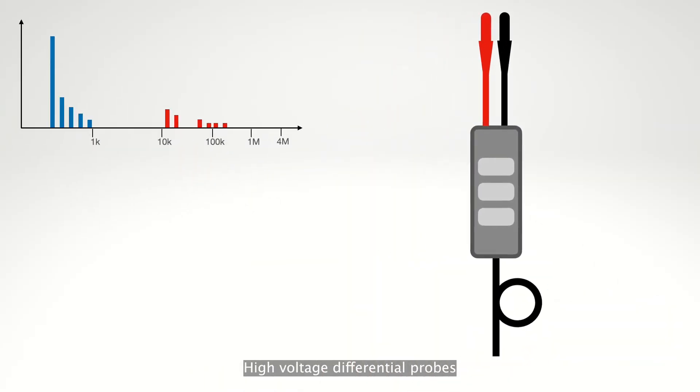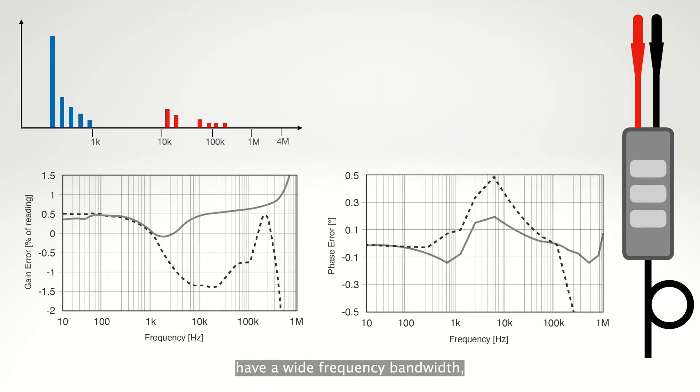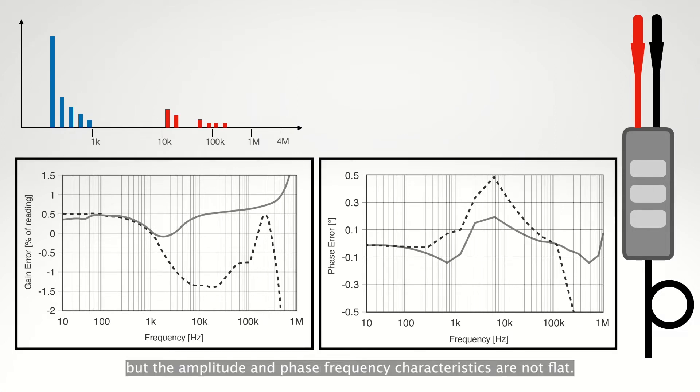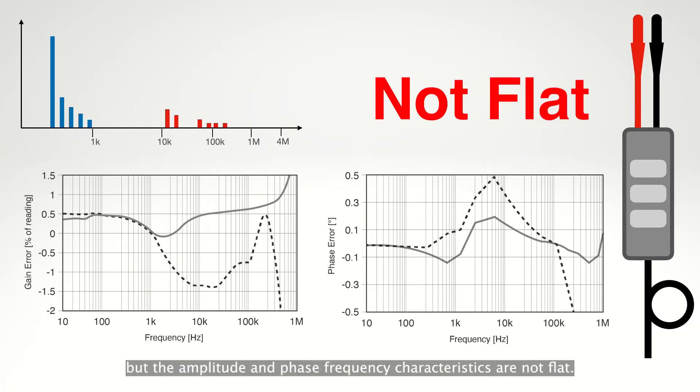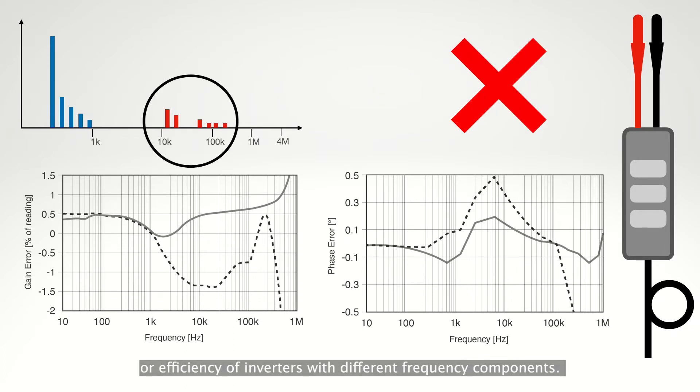High voltage differential probes have a wide frequency bandwidth, but the amplitude and phase frequency characteristics are not flat. Because of this, it is not possible to accurately measure the output power or efficiency of inverters with different frequency components.